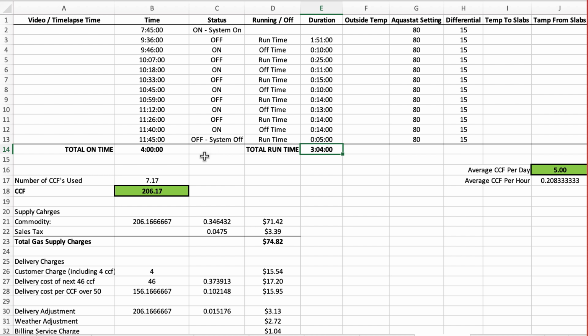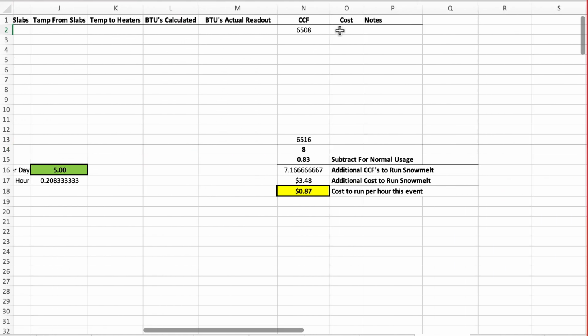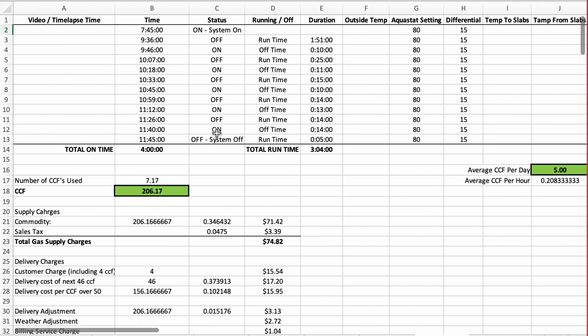I wanted to make the last video. I also wanted to get a really good idea for a full month of February of use. So I turned it on at 7:45 before I left for work. Read the meter, 6508. This one I remember watching from the cameras at work, and by 11:45 I remember looking on there and it was dry. The whole slab was dry, and there was no snow forecasted. It was already above freezing, so I shut it off.